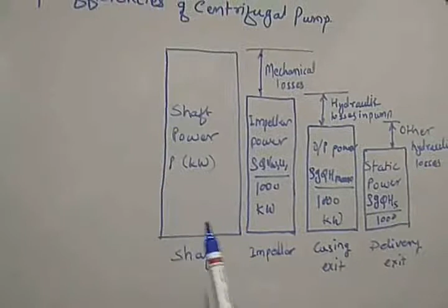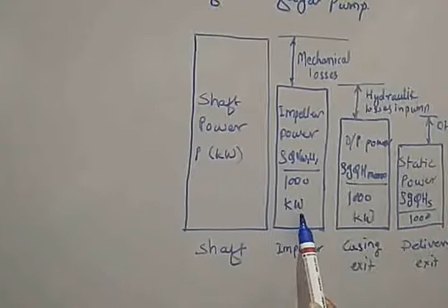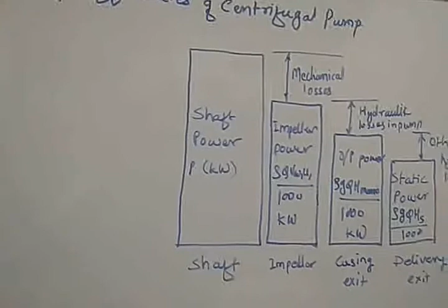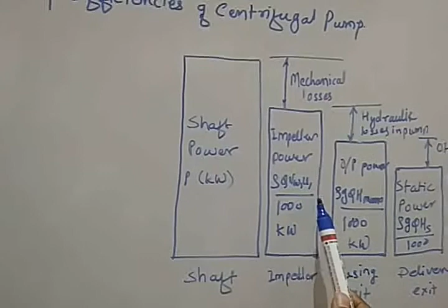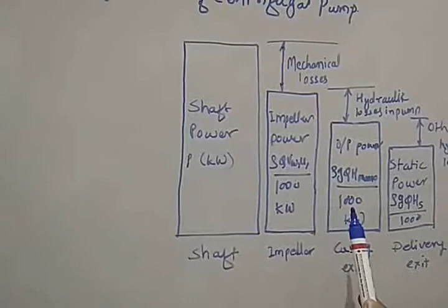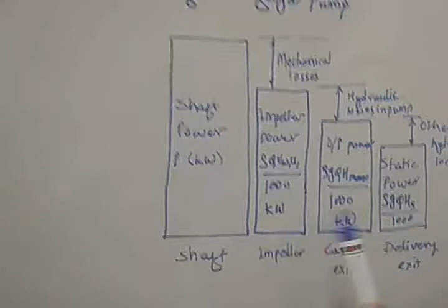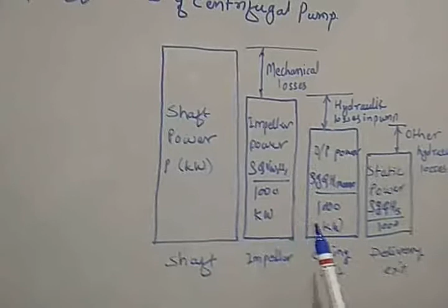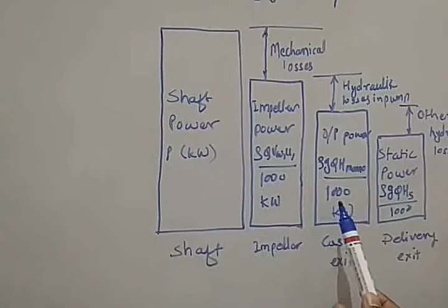From the shaft power given to the shaft to the impeller power, there are losses. These losses are nothing but the mechanical losses. Now in the impeller the power is given by rho Q g Vw1 U1 upon 1000, that is in kilowatt. At the exit of the casing we will have another power other than the impeller power, because of the hydraulic losses in the pump. Because of the hydraulic losses the power changes from impeller power to the output power, and that output power is nothing but rho g Q Hm upon 1000, where Hm is the manometric head.